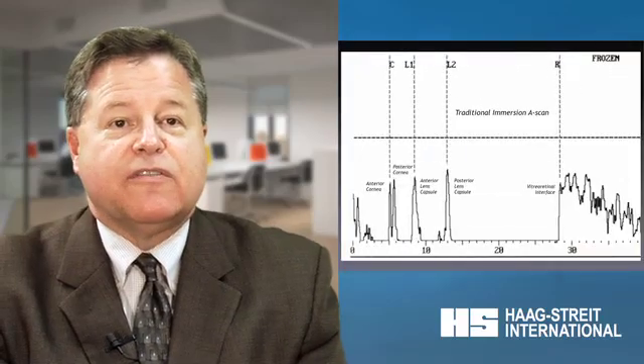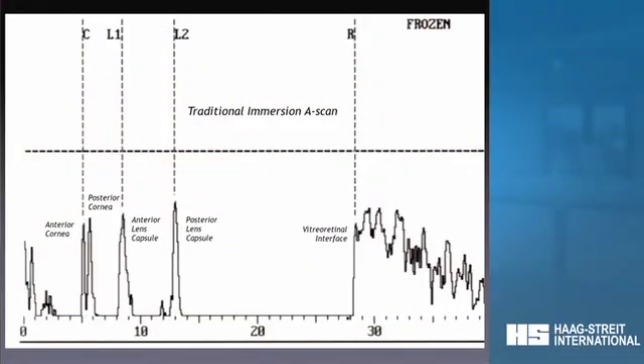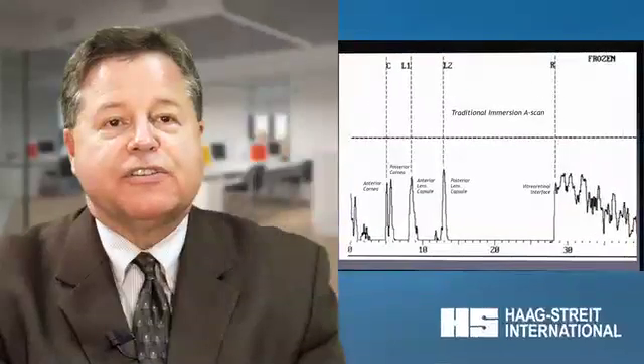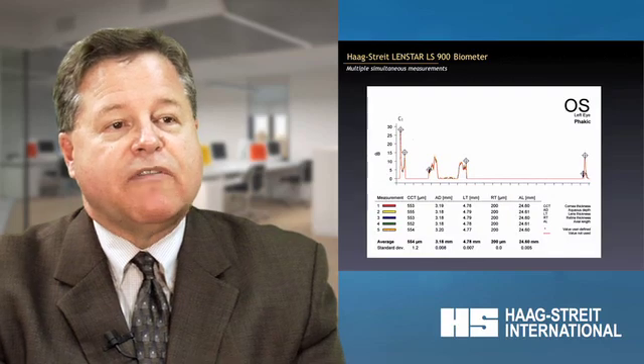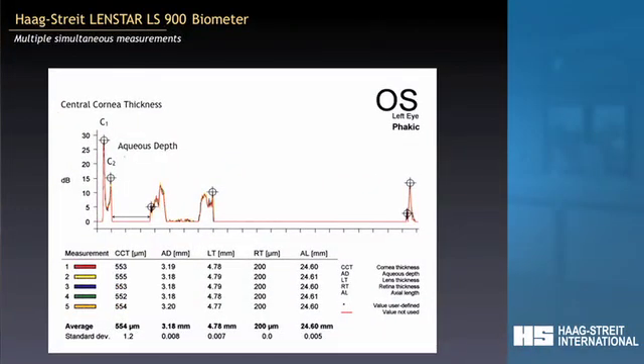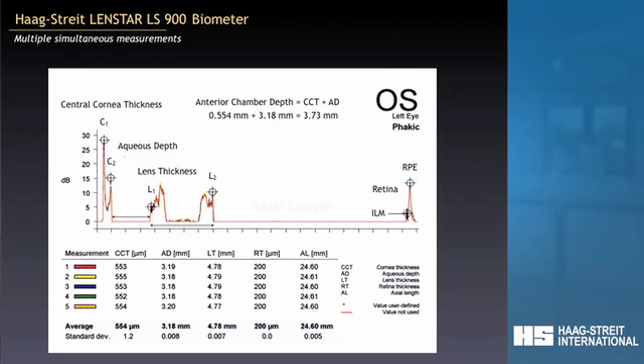As we all know, a traditional immersion A-scan looks like this, where we have graphic representations of the anterior lens capsule, posterior lens capsule, certainly the two spikes of the cornea, and the vitreo-retinal interface. For the LensStar, the graphic display is exactly the same. We have the anterior and posterior portions of the cornea, the anterior and posterior portions of the lens, and then the retina. We take all these together and we get the axial length.